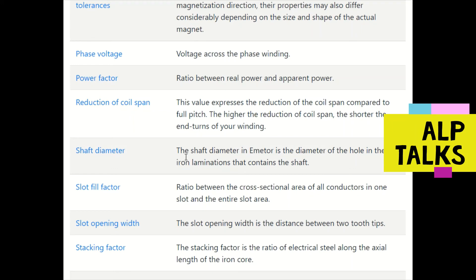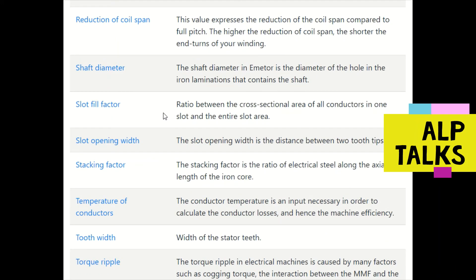Shaft diameter is the diameter of the hole in the iron laminations that contains the shaft. Slot fill factor is the ratio between the cross-sectional area of all conductors in one slot and the entire slot area. Slot opening width is the distance between two adjacent tooth tips.